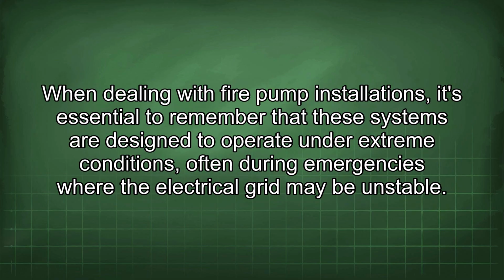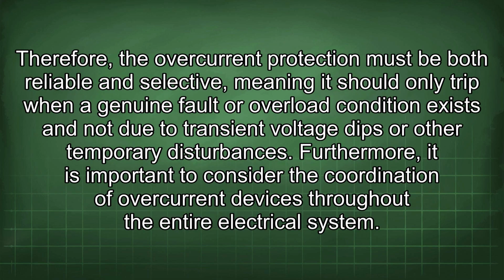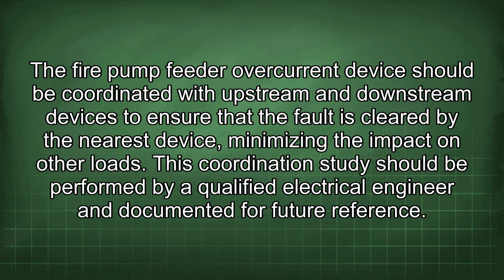When dealing with fire pump installations, it's essential to remember that these systems are designed to operate under extreme conditions, often during emergencies where the electrical grid may be unstable. Therefore, the overcurrent protection must be both reliable and selective, meaning it should only trip when a genuine fault or overload condition exists and not due to transient voltage dips or other temporary disturbances. Furthermore, it is important to consider the coordination of overcurrent devices throughout the entire electrical system. The fire pump feeder overcurrent device should be coordinated with upstream and downstream devices to ensure that the fault is cleared by the nearest device, minimizing the impact on other loads.